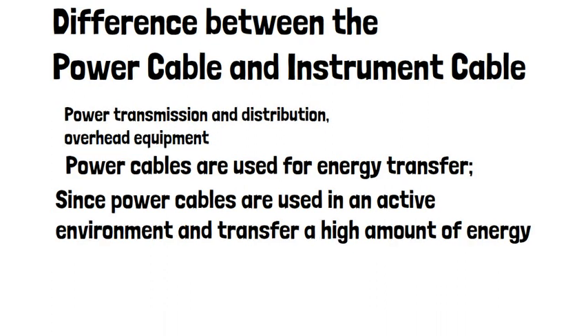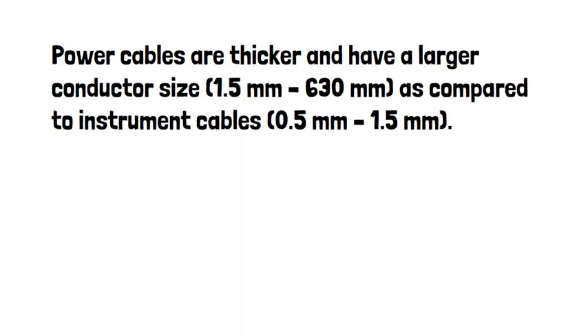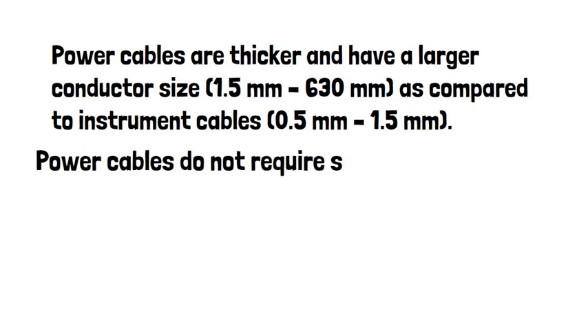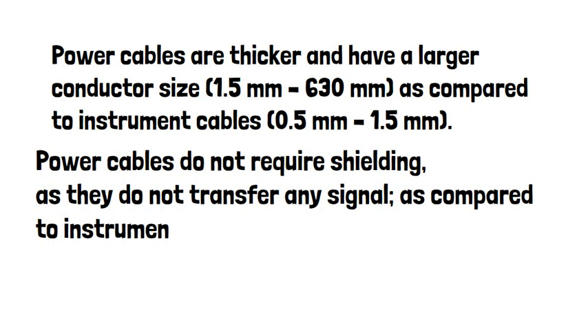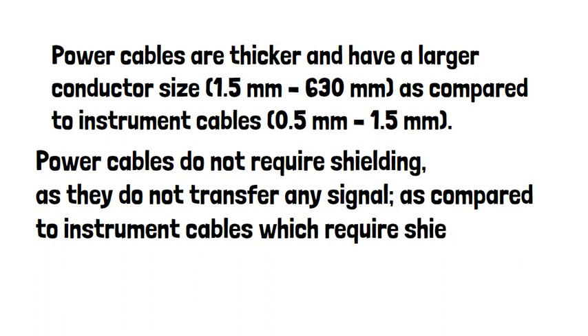4. Power cables are thicker and have a larger conductor size, 1.5 mm to 630 mm, as compared to instrument cables, 0.5 mm to 1.5 mm. 5. Power cables do not require shielding, as they do not transfer any signal, as compared to instrument cables which require shielding.